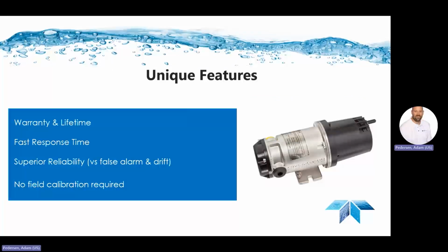So in summary, we do have a 15-year warranty on the IR source and a 5-year warranty on the electronic components. We also highlighted the response time curve earlier, which has some of the fastest IR response times in the industry. The dual wavelength and optic path design, along with the solid state infrared source, makes the GD10P one of the most reliable and maintenance-free IR combustible gas detectors in the industry, requiring no calibration.